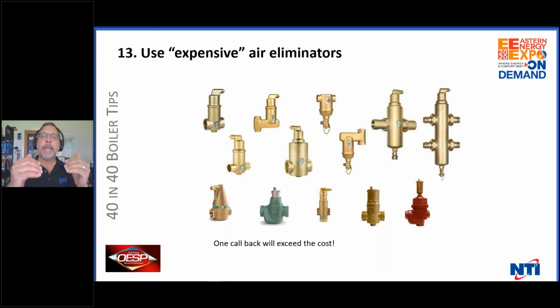Otherwise, that air-free or air-robbed water is going to seek it out and actually pull air in through your air vents. If you're not sure about that, or if you want to leave the caps off, Caleffi makes a nice little anti-siphon device, a little check valve that you stick underneath all your air vents, and it'll prevent it from pulling air back in. Otherwise, they will pull air in using these air eliminators.